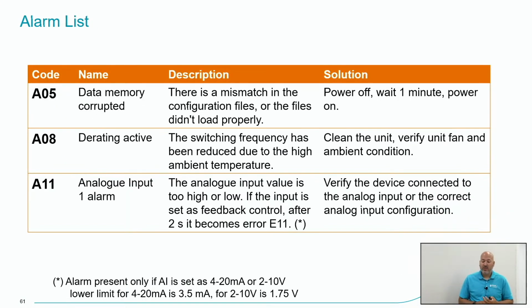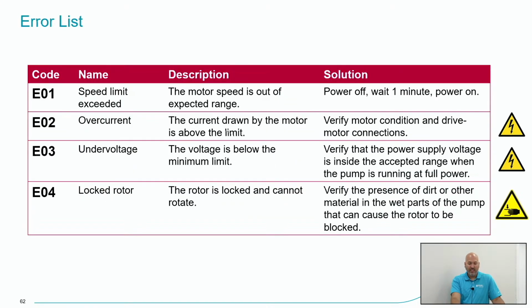There would be an alarm list, so you can find this in the IOM. You'll actually also be able to find this right on the VFD HMI itself. But any alarms, like I said, are going to be indicated by a yellow flashing light. They're going to start with an A code followed by 2 digits. And associated with that, you have a name, description, and potential solutions on how to fix what the alarm is. And then similarly with errors, you'll find what they are by a flashing red light. There'll be an E code for error followed by 2 digits, and similar structure again: name, the description of that error, and some solutions on how to resolve it.